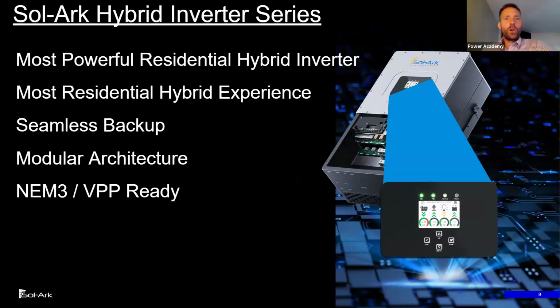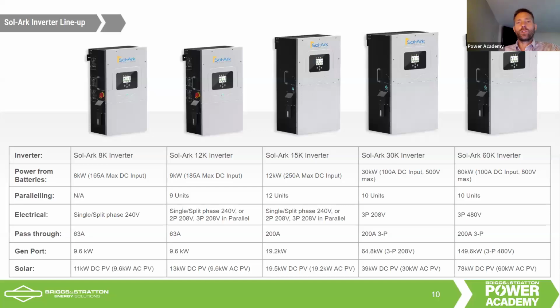What makes it so great is it's kind of an all-in-one inverter. So it's got everything built into it. So you've got your charge controller built in, you've got your monitoring app, your communications platform built in. There's no external gateway. It's got your MPPTs, your charge controller. You've got your generator integration port built in. And you have seamless backup of 5 millisecond transfer time. It's NEMA 3R rated. It's NEM 3 VPP virtual power plant ready. And there's a lot of great things to say about the Sol-Ark inverters, particularly their software. So they've got a lot of experience getting things right, and these inverters just work and continue to work, and are very consistent.